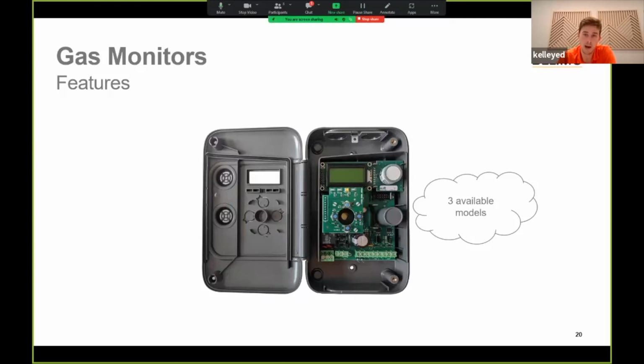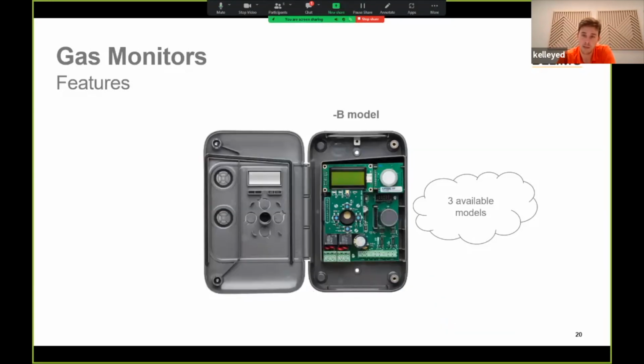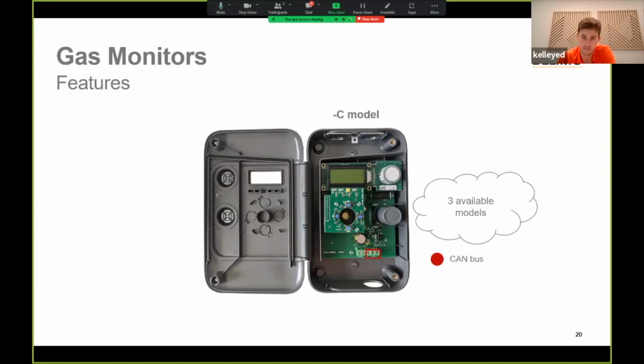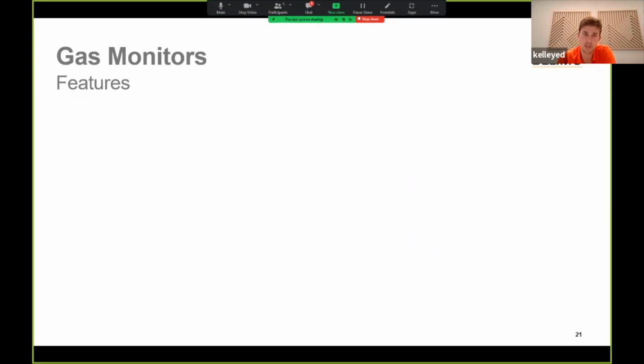So this is an A model that has CAN bus and BACnet for communication, 1 relay and 2 analog outputs for direct control. We have a B model that offers CAN bus and BACnet for communication, 2 relays for direct control. And we have a C model that just has CAN bus. All right, so the question after that is, why do we offer 3 different models, and why do we offer 1 model specifically that just has CAN bus and nothing else?